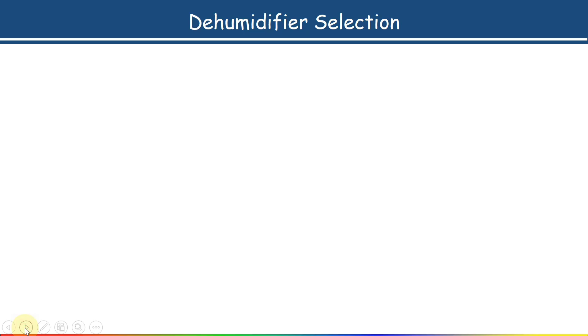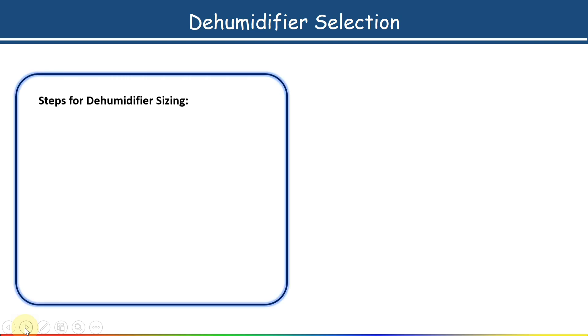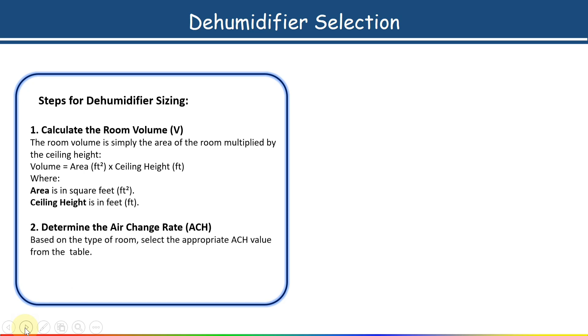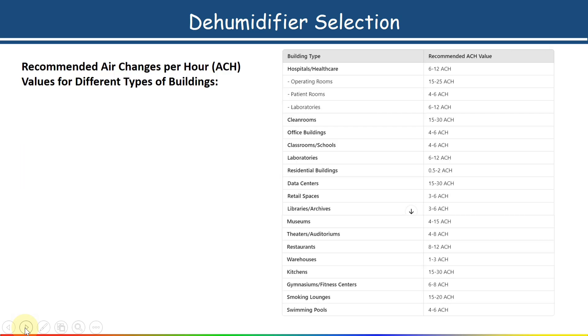Here I will show you the dehumidifier selection criteria — the steps we have to follow for selecting a dehumidifier. Similar to what we discussed in humidifier sizing, the first step is to calculate the room volume in cubic feet, which you will get from the drawing. The second step is to determine the air changes per hour (ACH) rate — based on the type of room, select the appropriate ACH value from the table, where recommended values are given for different types of buildings.